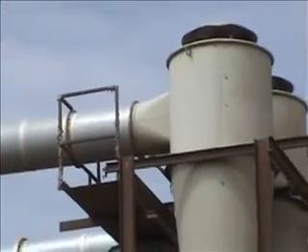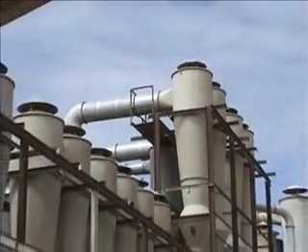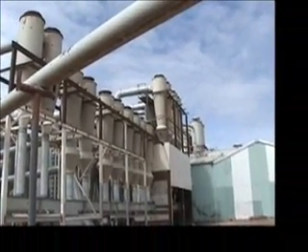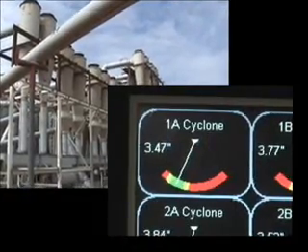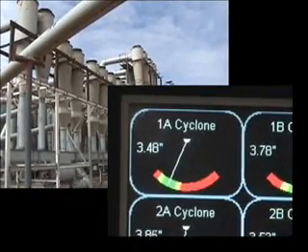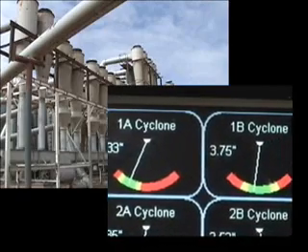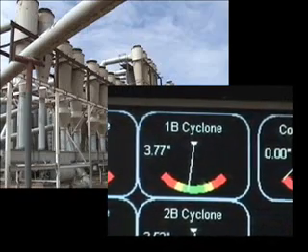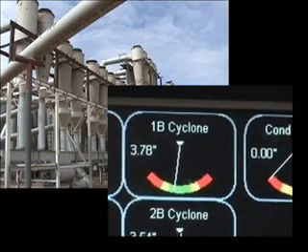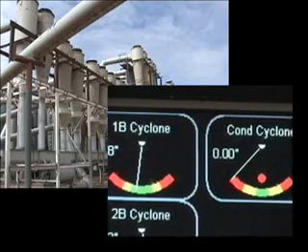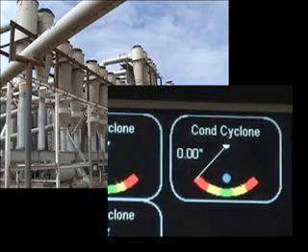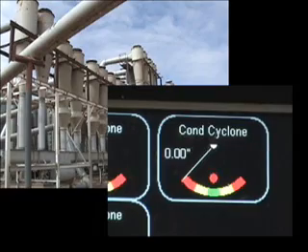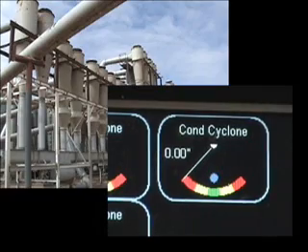You don't need to go farther than your nearest air quality representative to understand the importance of monitoring pressure on air filtration cyclones at a cotton gin. A natural location for monitoring static pressure on a cyclone is at the inlet to the cyclone. Besides playing the role of a responsible neighbor, there are gin production issues at stake as well. If cyclone pressure rises above a certain limit, it frequently indicates a choked cyclone. This, in turn, is a common cause of low air flow in the gin's drying and pre-cleaning system, which can directly affect production, energy efficiency, and grade.